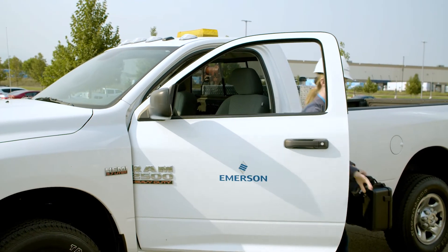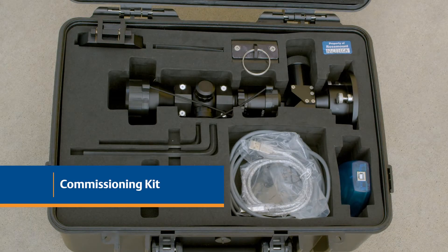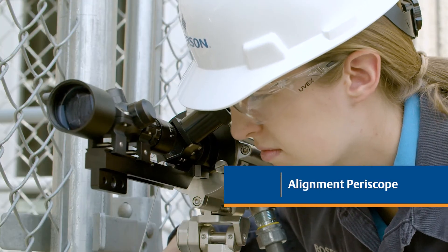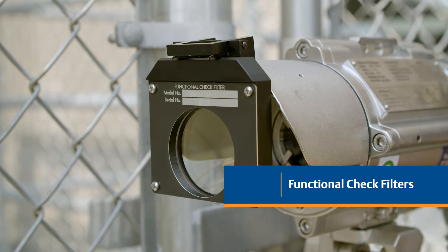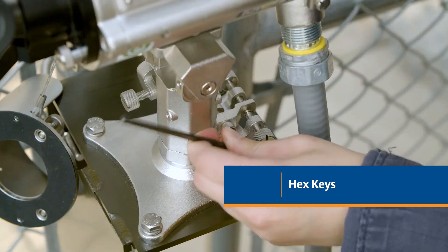The Open Path Gas Detectors can be installed by a single person. The commissioning kit provided with the Rosemount Open Path Gas Detectors contains all the necessary equipment needed to perform the installation. The kit includes an alignment periscope, also known as an alignment scope, to facilitate source and receiver alignment, and a magnetic mode selector for selecting receiver operating mode. One or two functional check filters utilized for both installation and periodic functional testing depending on your product.